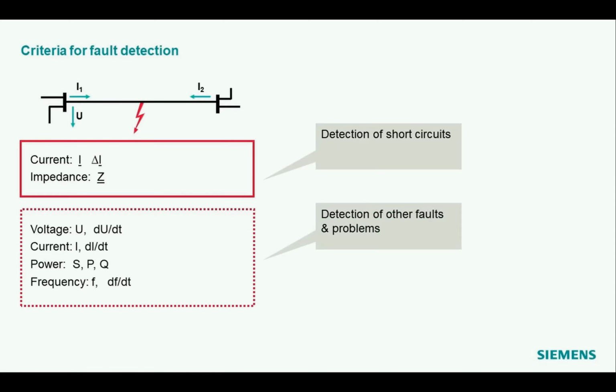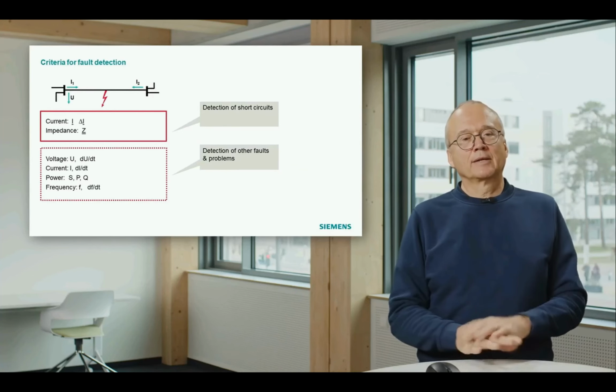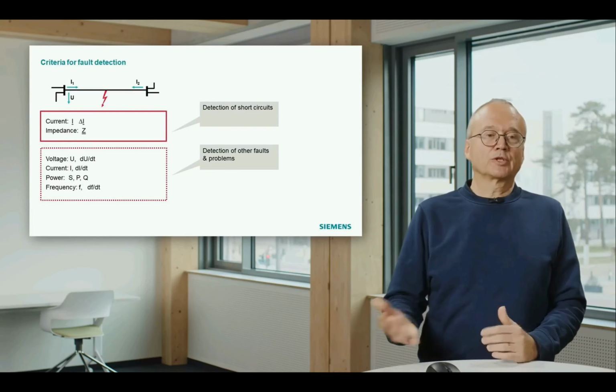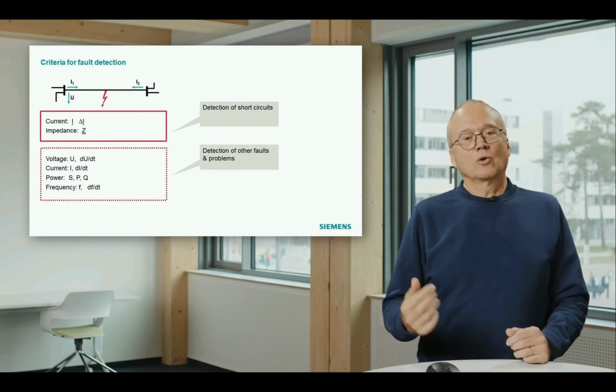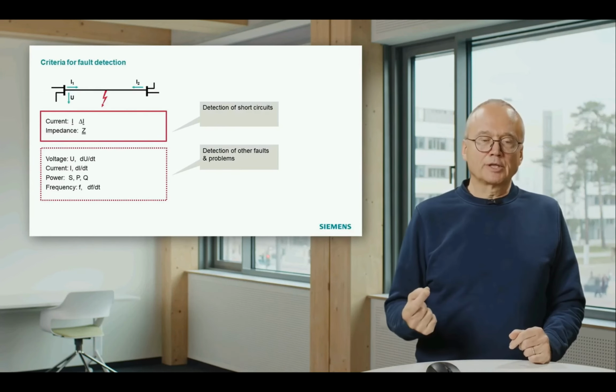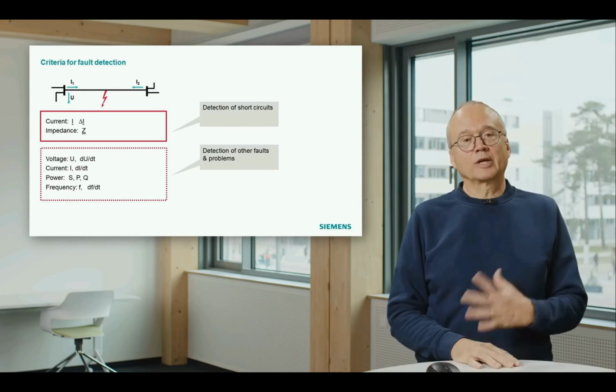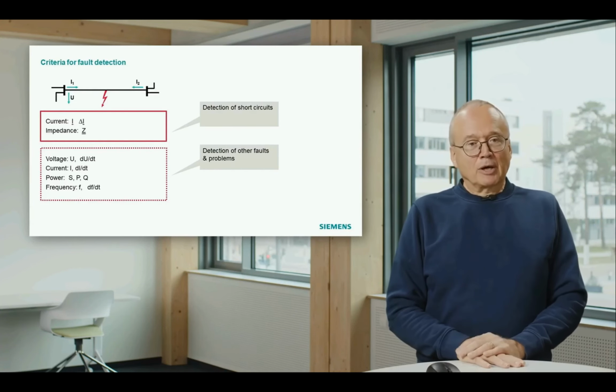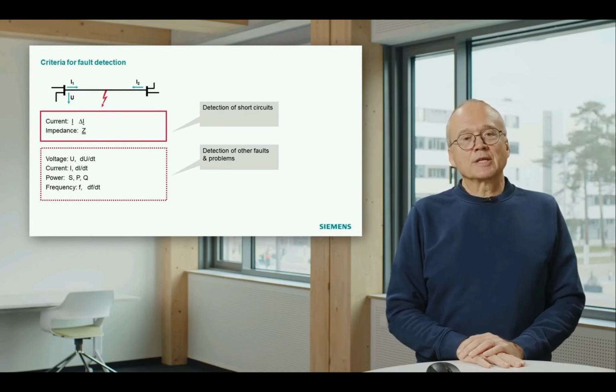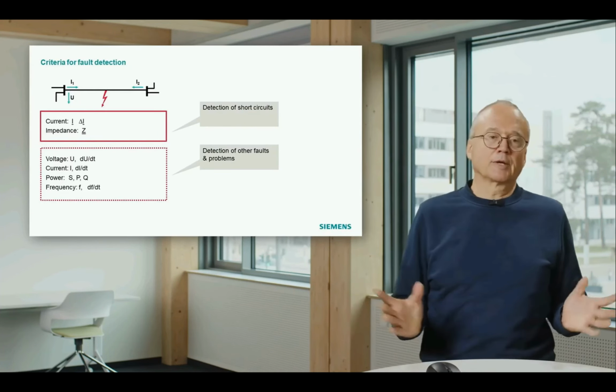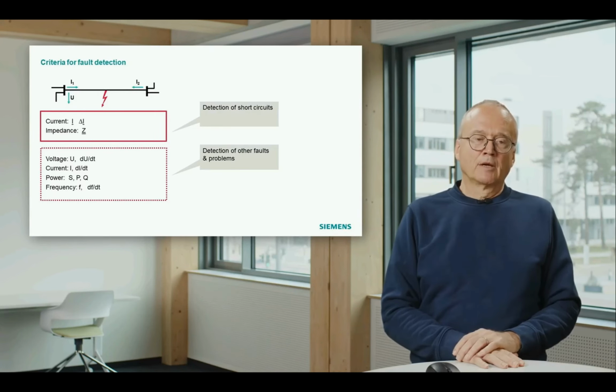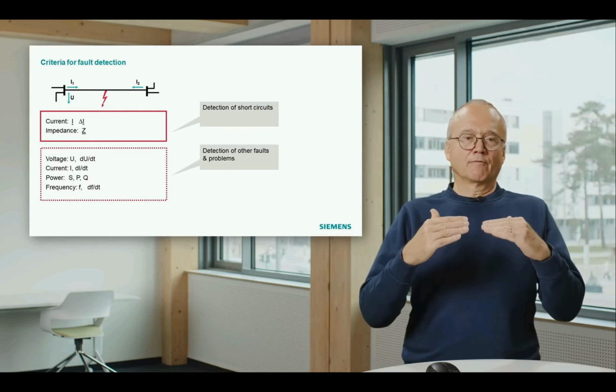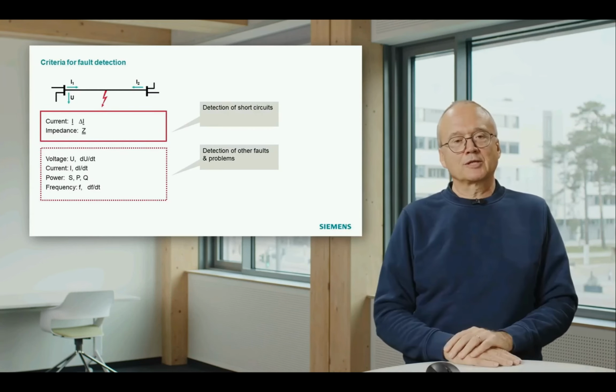I mentioned already in the beginning, we have also other types of faults, and to detect them, we need other principles. We can look at the voltage. We have to detect over voltages, under voltages, also the rate of change of the voltage, and the current is sometimes required. We can measure the power, apparent power or real power, and also the frequency is used as a criterion, and also the rate of change of frequency. Maybe the frequency, for instance, is often used for load shedding. You may know that normally the frequency is very close to nominal frequency, 50 Hertz or 60 Hertz.